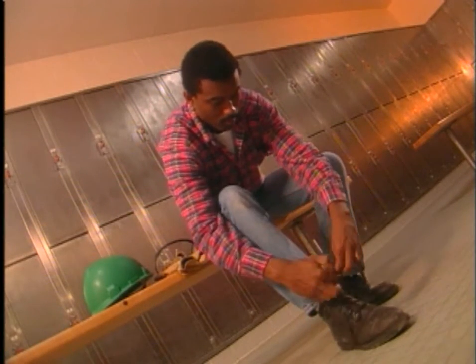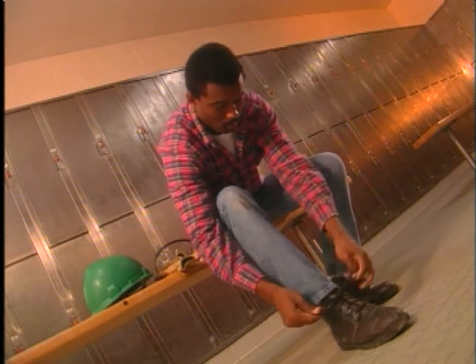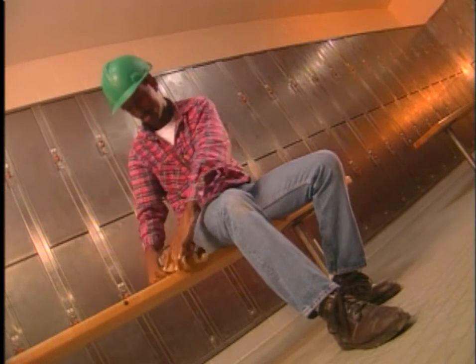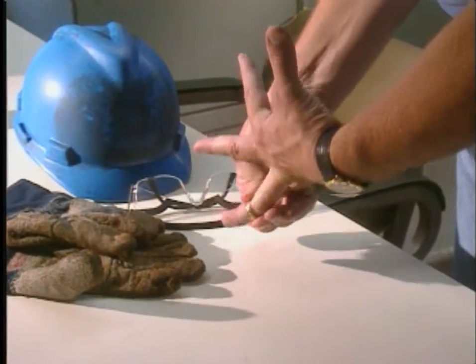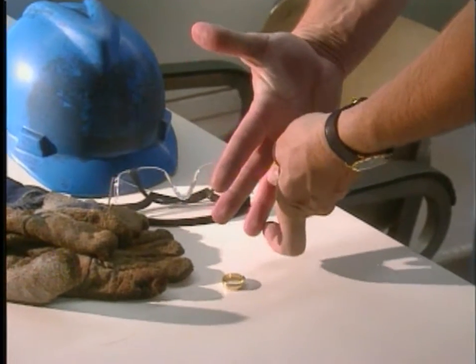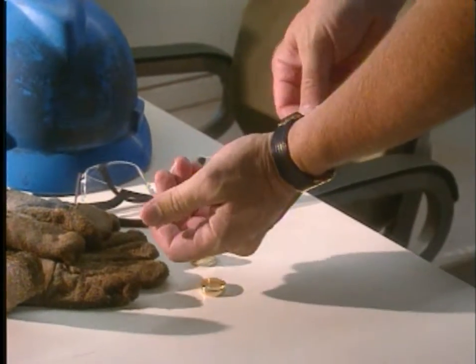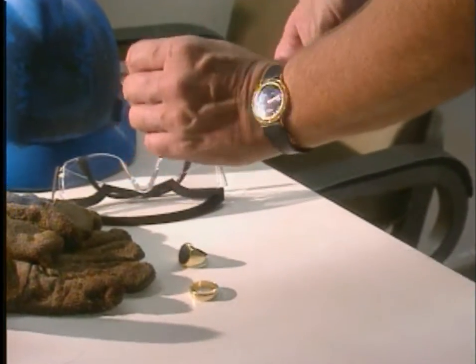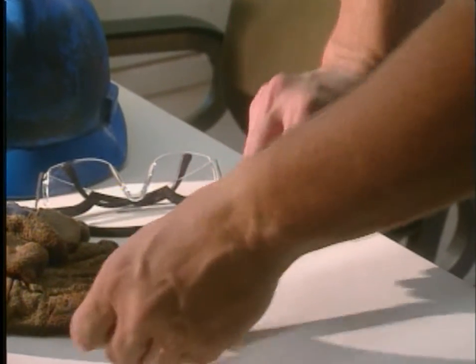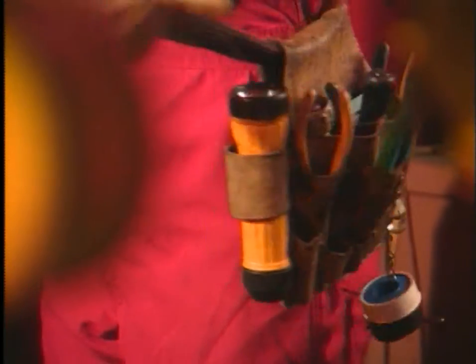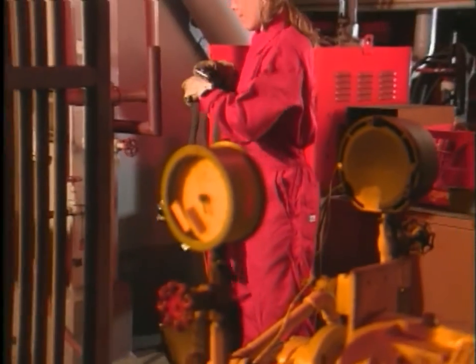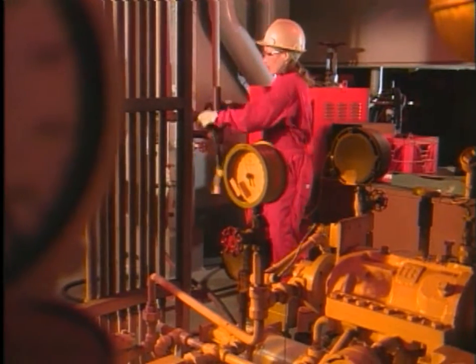PPE starts with the right clothing. You'll need a good pair of safety shoes with insulated soles and heels, comfortable clothing with buttoned shirt cuffs, and no neckties or scarves. Remove all jewelry, rings, and metal wristwatches. Gold and silver are excellent conductors and can make you part of a live circuit. And a short circuit through jewelry could ruin sensitive electronic circuits as well as kill you. A standard electrician's tool belt is okay, but remember that metal rivets can conduct electricity. In tight spaces, take the tool belt off first. Dangling tools can drop into operating equipment or across electrical connections.